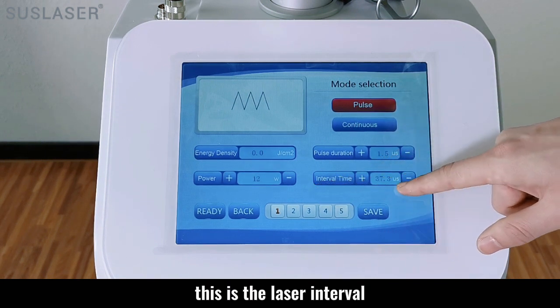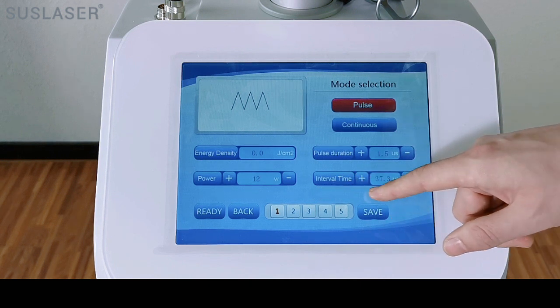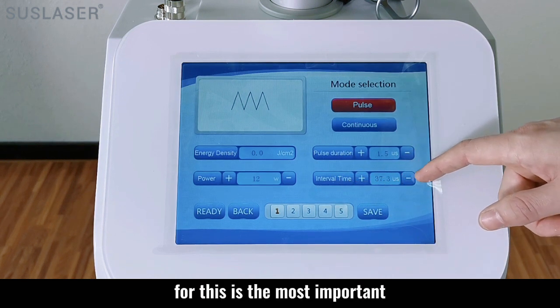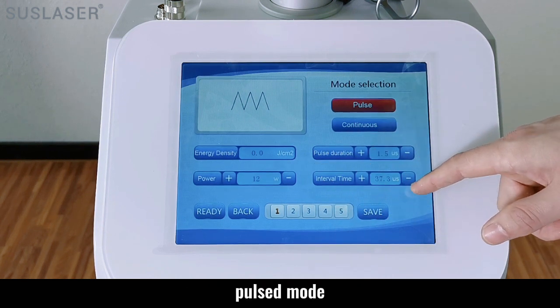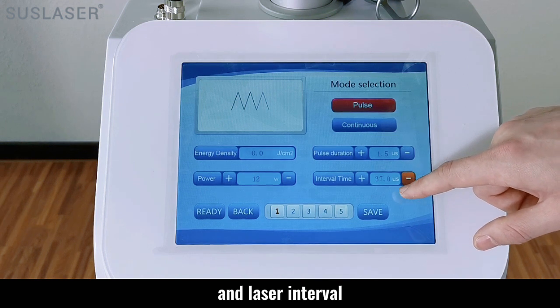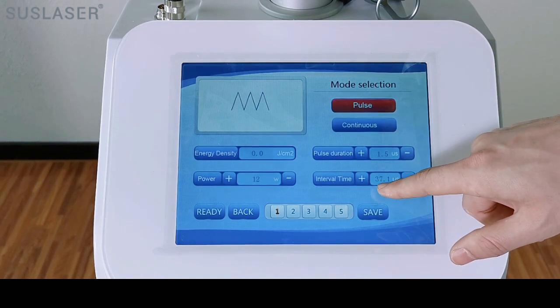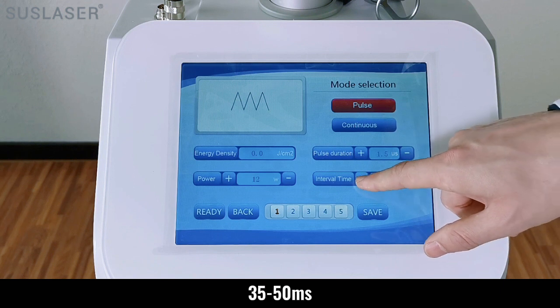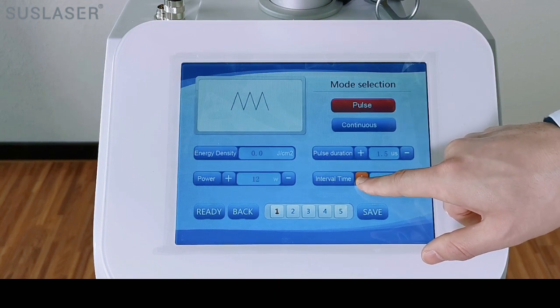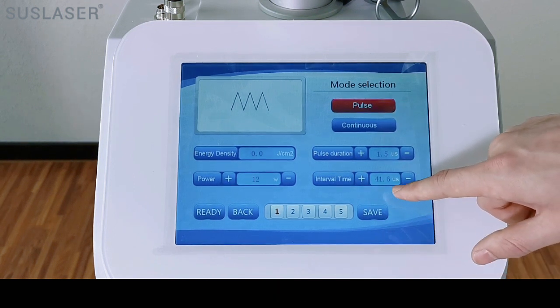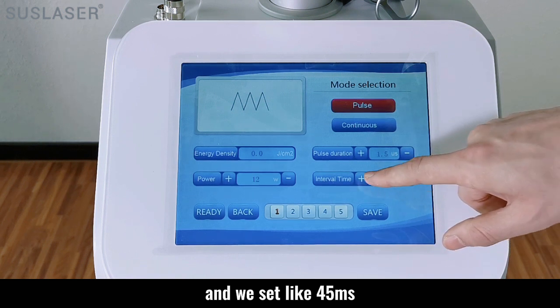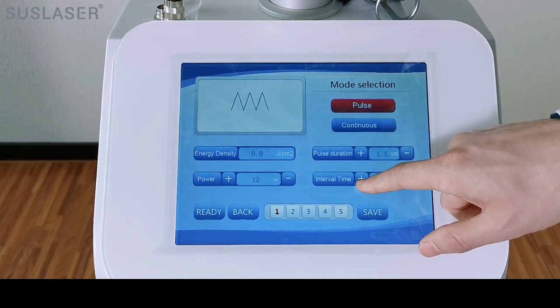This is the treatment interval. This is the most important for the pulse mode. The treatment interval we can use from 35 to 50, and we set like 45.